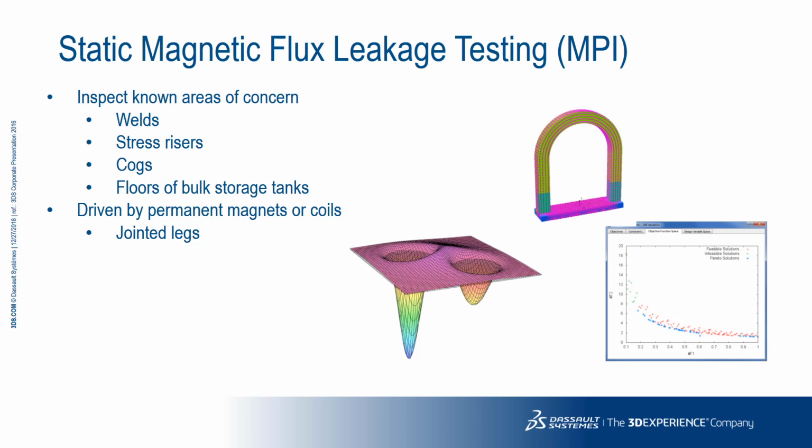This allows for scanning on both sides of the wall. Using a lower field might require multiple passes to fully determine the location of the flaw, and this can be difficult because of residual magnetism in the steel after passing over the MFL scanner. This type of device is commonly used on structures such as storage tanks, where the walls or floors are subject to corrosion.